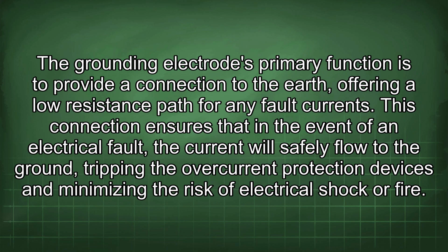The grounding electrode's primary function is to provide a connection to the earth, offering a low resistance path for any fault currents. This connection ensures that in the event of an electrical fault, the current will safely flow to the ground, tripping the overcurrent protection devices and minimizing the risk of electrical shock or fire.